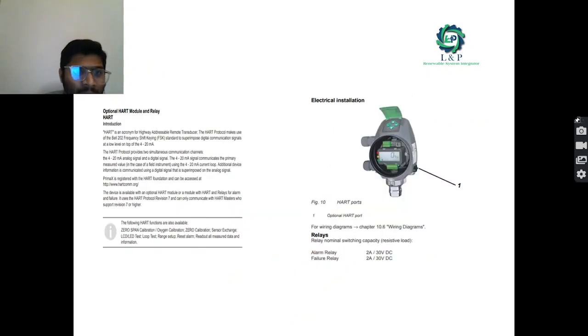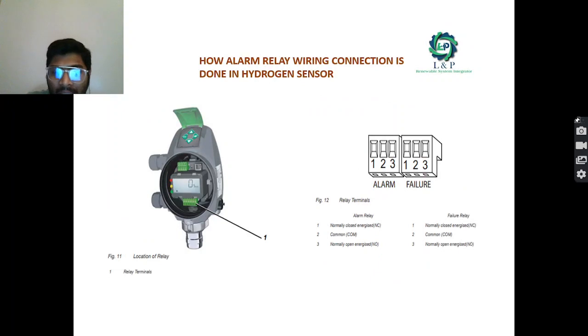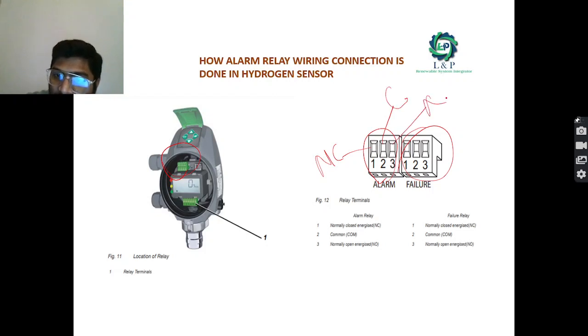Next, if you want to connect with the HART module or the relay, you can do the electrical wirings like this. Okay, as you can see here, the alarm relay is capable of operating with 30 volt DC with a 2 amps rating, and the failure relay is also 30 volt DC 2 amps. Okay, so as we told earlier, apart from the basic connection, if you want to take the alarm output or the failure outputs, we have two relays available. Okay, which has a three terminal block. Okay, the first 1, 2, 3 you can use for alarm. Okay, so the first one will be the normally closed, and 2 will be the common point, and the 3 will be the normally open point.